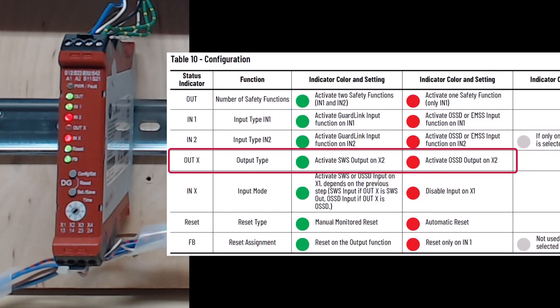The out LED is red, because you want to configure the X2 terminal to be an OSSD output. You would change it to green if you wanted the output to be a single wire safety output. Short press the select button while the color is red.